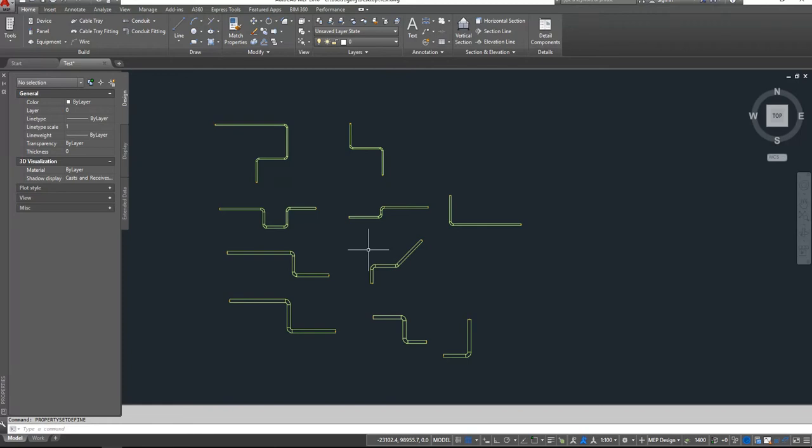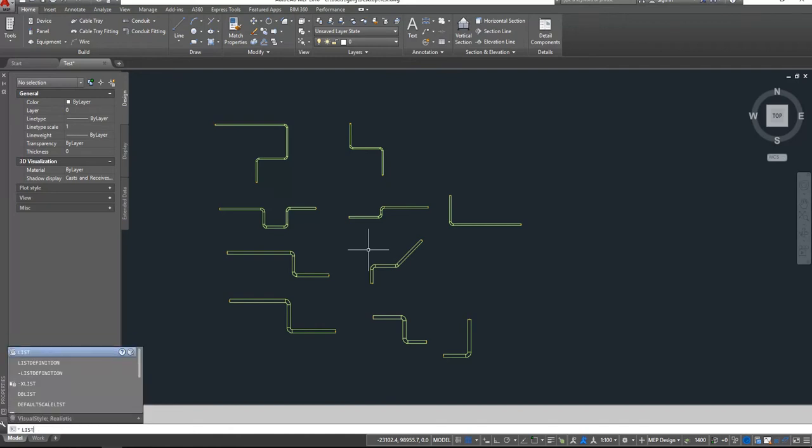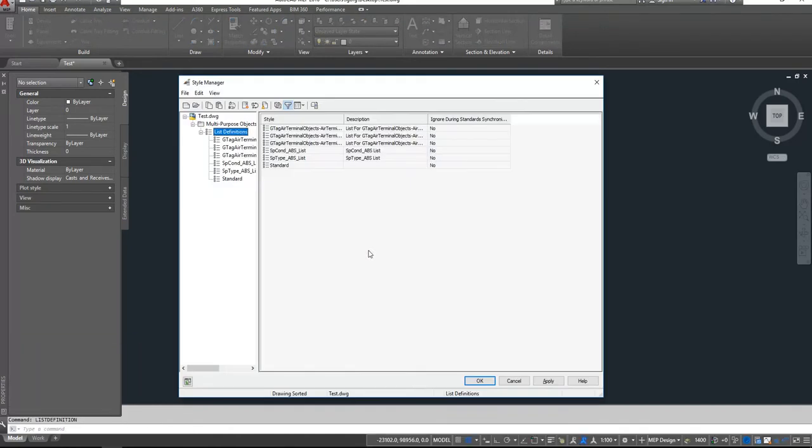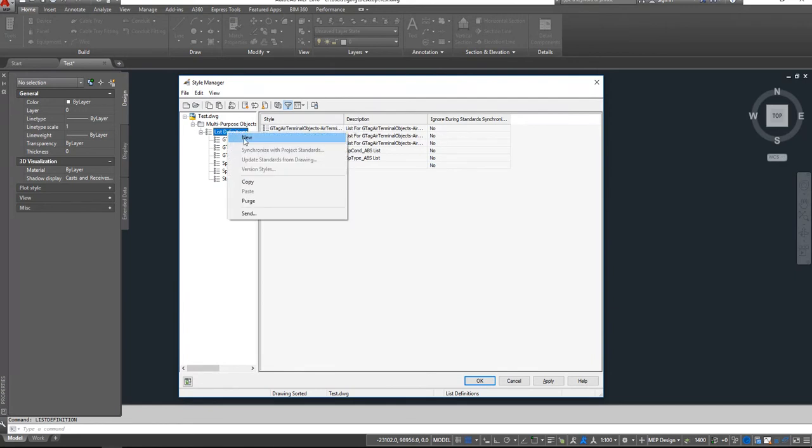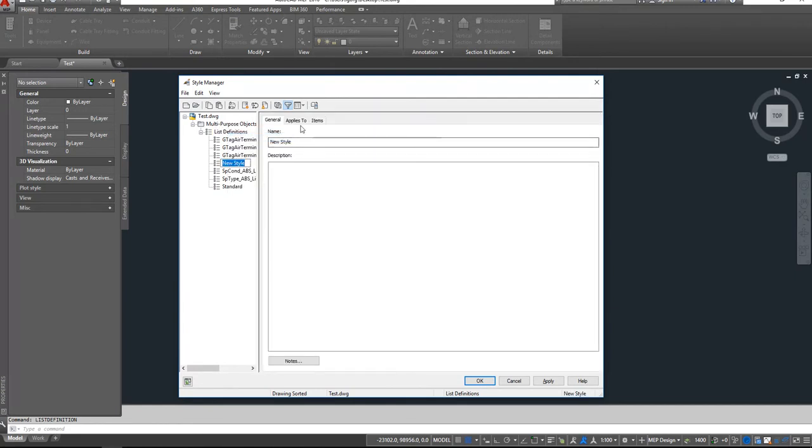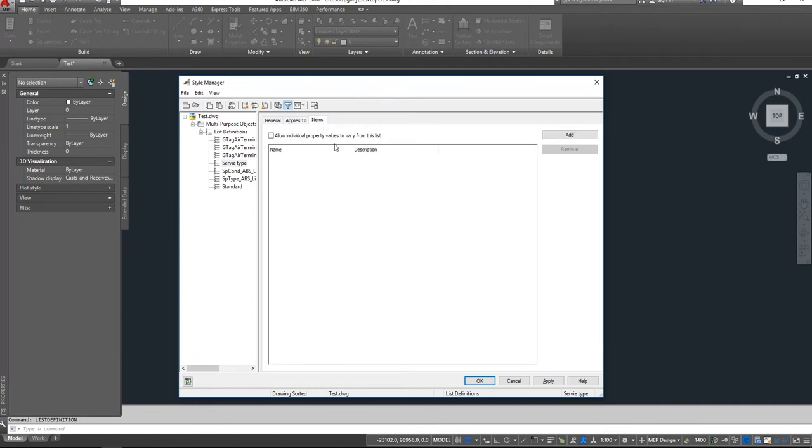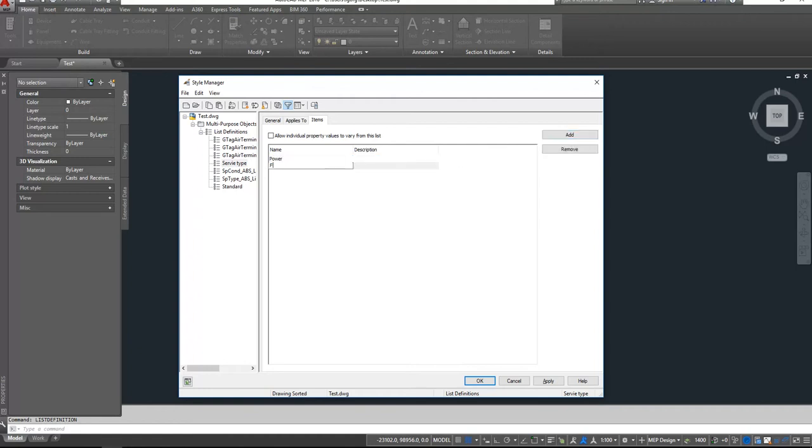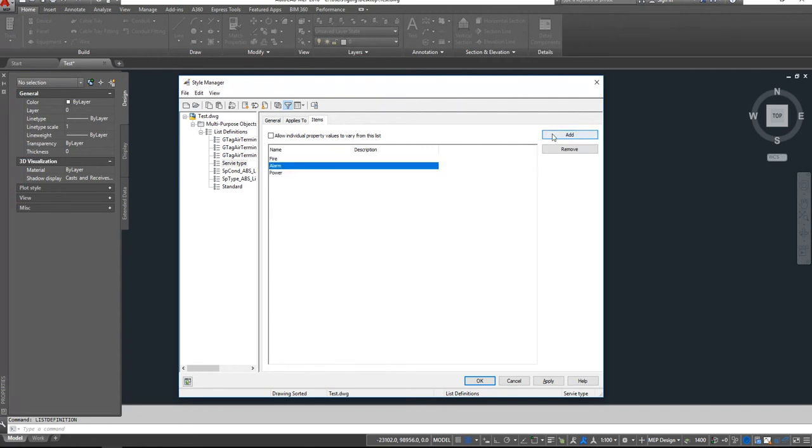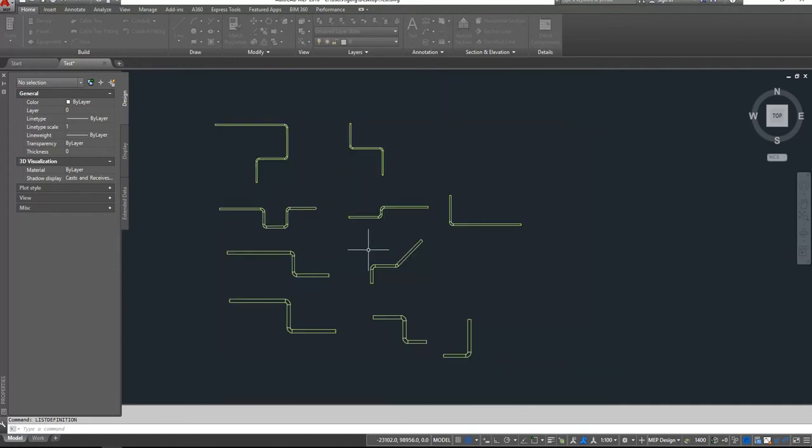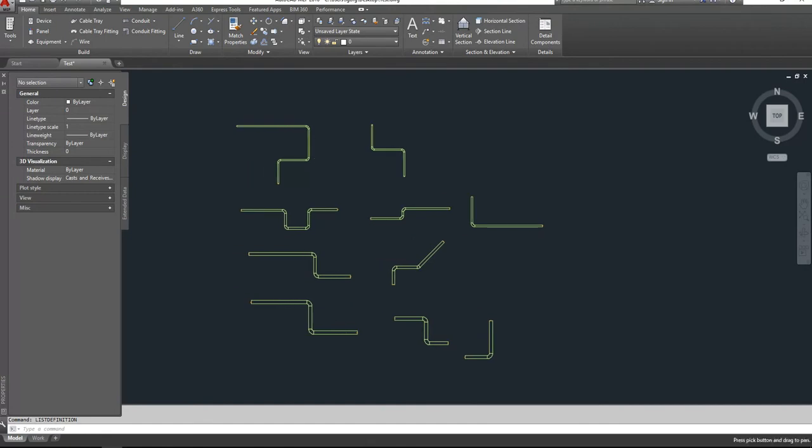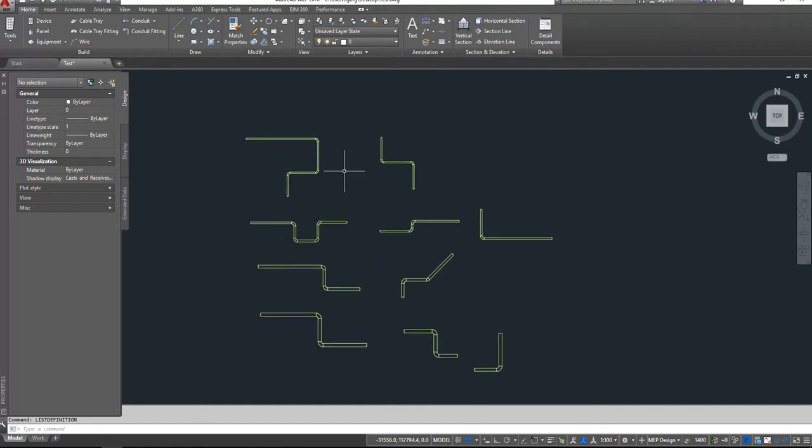Then if we want to create a group of service type cable trays, we have to create some list definitions. So we will go to List Definition and here we will create a new list of definitions. We will say it's Service Type. It applies to manual property definition and we can add items, so we can write Power, Fire Alarm, and for example IT. Okay, Apply, OK.